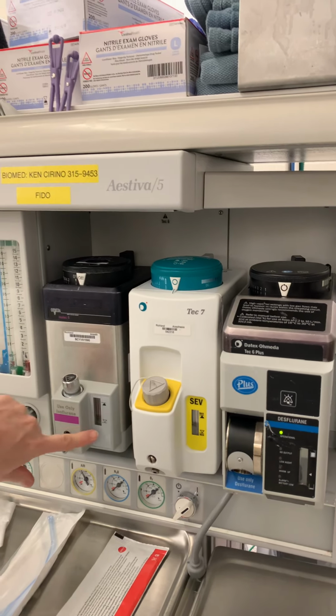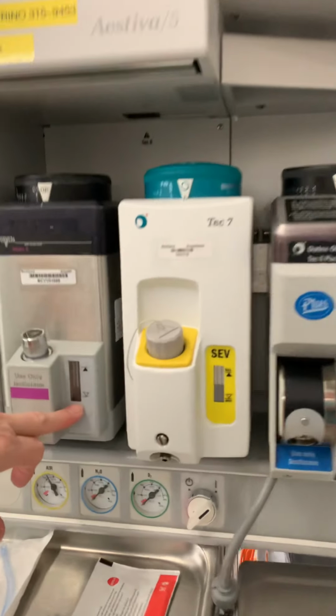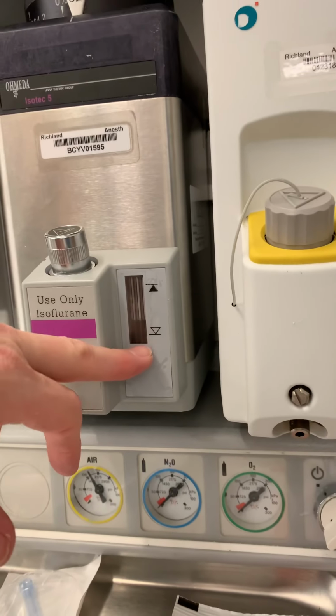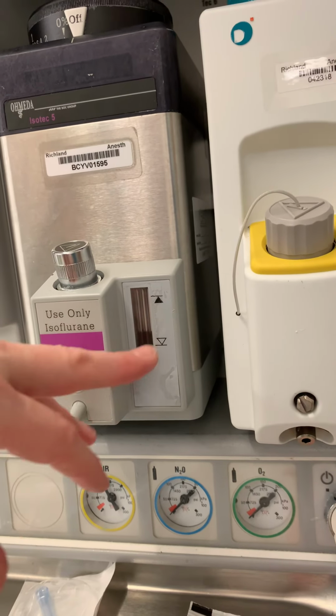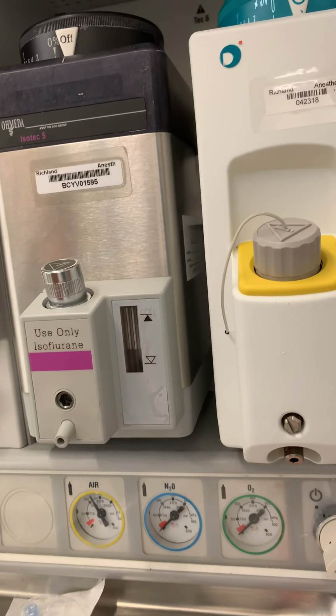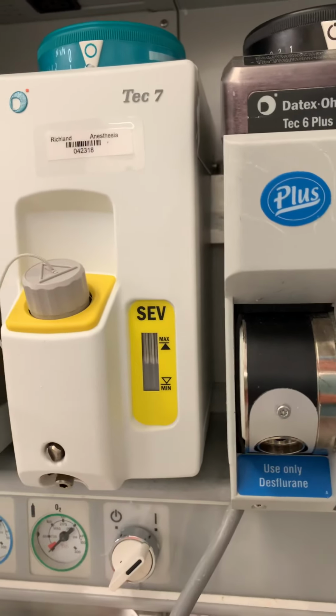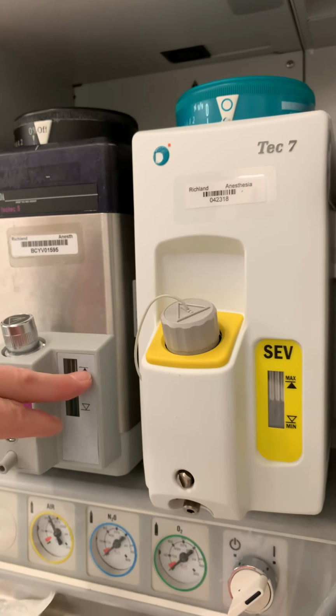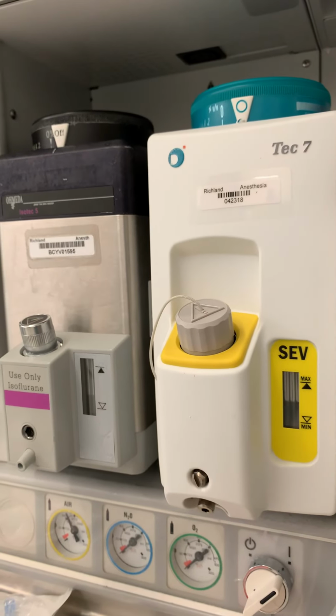And then this is the opportunity to make sure that your vaporizers are full. So here's a gauge that shows you in the dark how much potent agent you have in your vaporizer. This one's about halfway full, this one's about halfway full, and you can see the max lines. You don't want to go over the max line of each vaporizer.